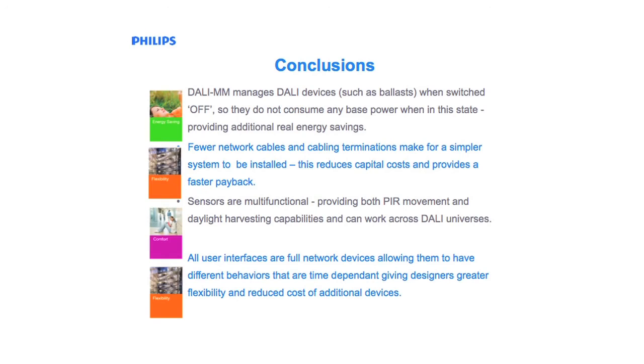Sensors are multifunctional and capable of performing both PIR and daylight harvesting capabilities. At the same time, they communicate directly onto the DALI universe, which can then be translated onto the Dynet network, making the sensors capable of controlling any other Dynalite device on the system. All user interfaces are now fully networked onto the DALI system, allowing them to be configured by the head-end software, and are able to be manipulated by timer-based events, giving them different features and functions as required through the 24-hour cycle of an office space.